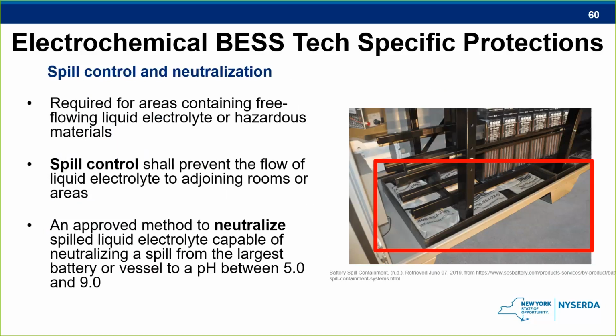Some battery energy storage systems use liquid electrolytes, which can be corrosive. They can burn the skin and damage PPE, and first responders should follow their department's standard operating procedures when responding to corrosive spills. Some of these chemistries can contain corrosives that are upwards of 1,000 gallons. These systems should have secondary containment, and in some cases may even have tertiary containment. Lithium-ion batteries do not fall into this category because they do not have liquid electrolyte.